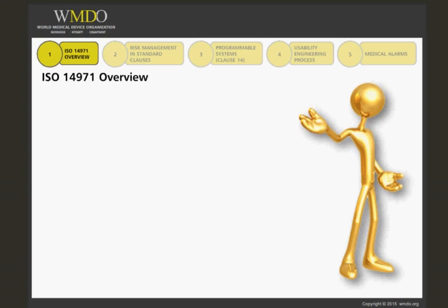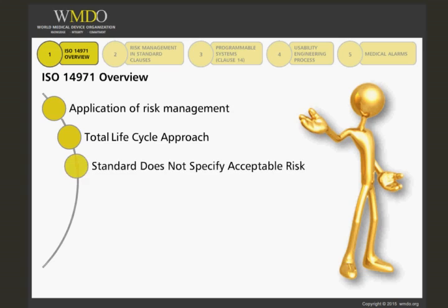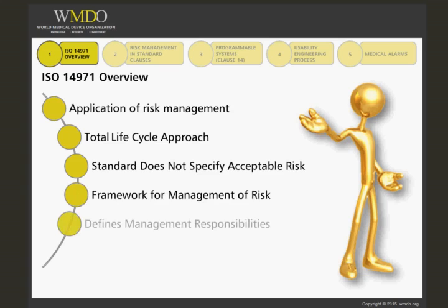To use Edition 3.1, it is essential that you are familiar with the ISO 14971 standard, as covered in depth in the other courses of the WMDO library. As a brief reminder, ISO 14971 provides a specific outline of the application of risk management to medical devices. It addresses a total product lifecycle approach. ISO 14971 does not specify what represents an acceptable risk — acceptability is determined by the manufacturer for each device. It provides a framework for the management of risk and defines management responsibilities related thereto.